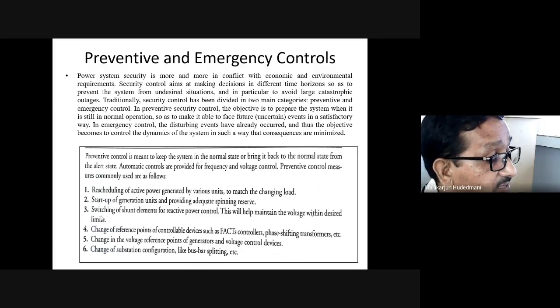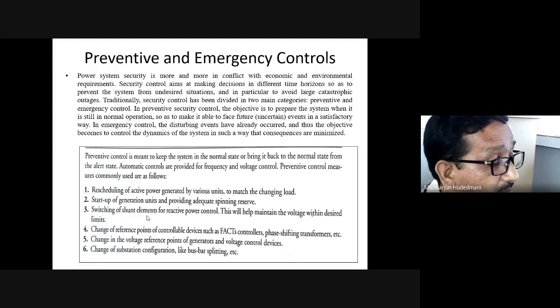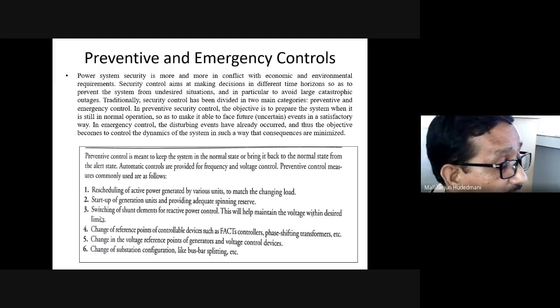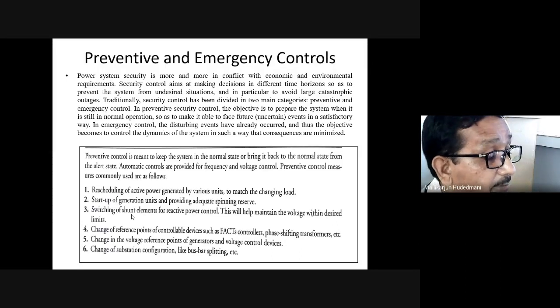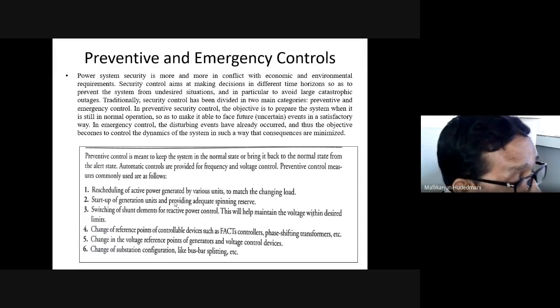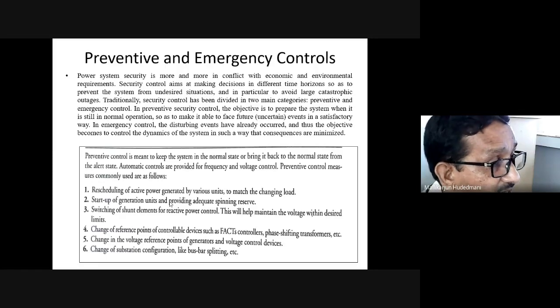By the time it is needed, it is ready to serve you. This way, the preventive mechanism helps us to make the requirement fulfilled. Then switching off shunt elements for reactive control. Remember, any reactive power, switch on, switch off if required, so that reactive power management must be appropriately controlled.